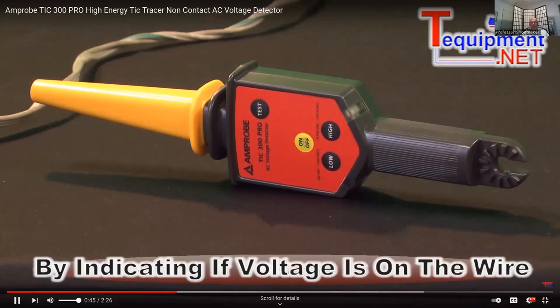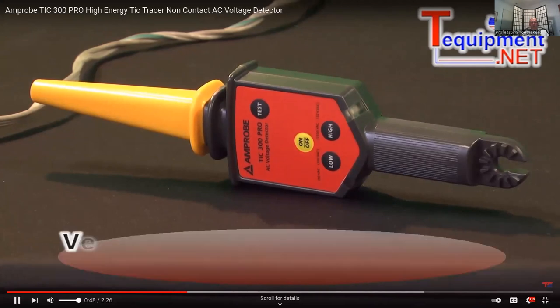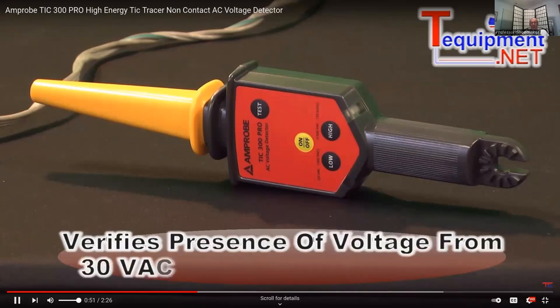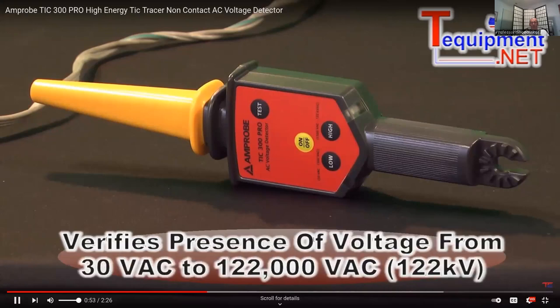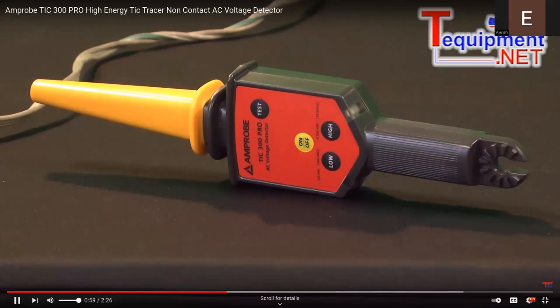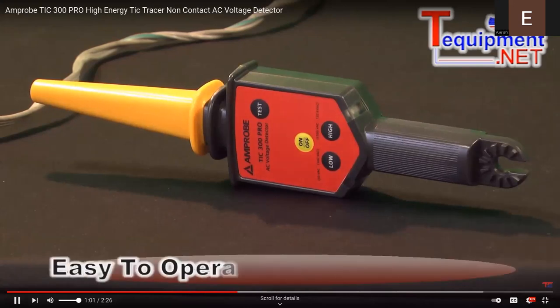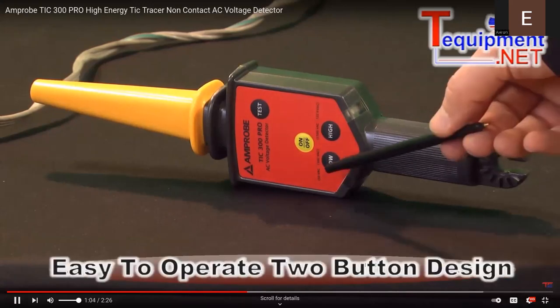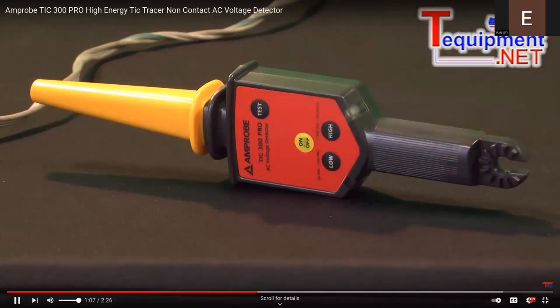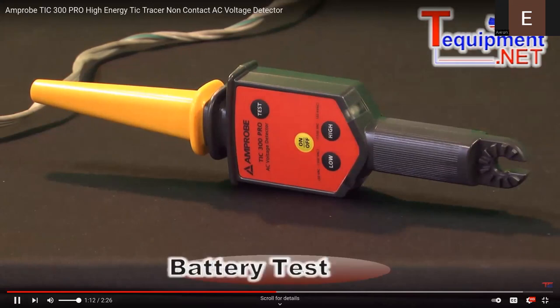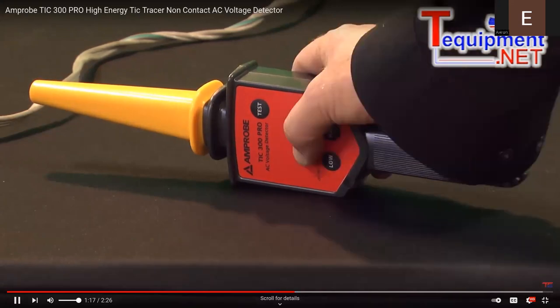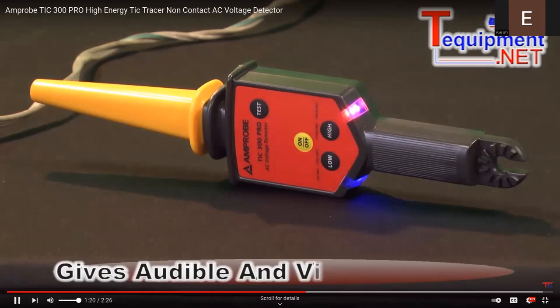There's two ranges. There's a low range, which detects voltage from 30 volts AC up to 1500 volts AC. There's a high range, which extends this from 1500 volts AC all the way up to 22k volts AC. We have two buttons on the front, which tell us which mode we're on, either the low or the high. We also have a test key. What that's for is to make sure that the batteries are good. You want to make sure that your batteries are good when you decide that something is either powered on or powered off. So if I turn the unit on, what it does is it gives me both an audible and a visual indication that we have voltage on the line.